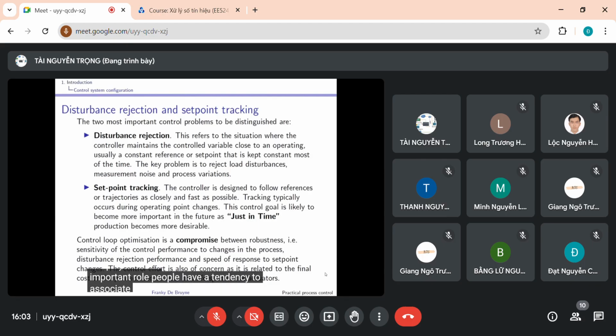People have a tendency to associate the controller with set point tracking, but we'll see that the disturbance rejection capabilities of the controller should not be neglected. Control loop optimization is the art of finding compromises between disturbance rejection performance, tracking performance, but also robustness. Robustness is the sensitivity of the control performance to changes in the process. The control effort or control energy is also of concern, as this control energy is related to the final cost of the product and to wear and lifespan of the actuators.